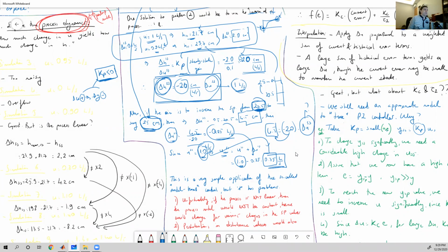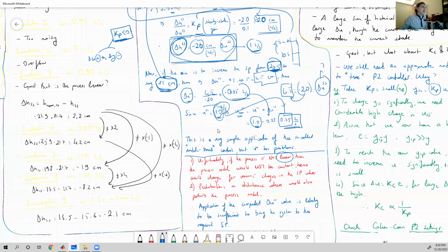Now, the most important problem here is this works only if the process is linear. Because if the process is nonlinear, such as the one that we have, the process parameters are likely to change from operating point to operating point. And I have already shown you that tau significantly changes from operating point to operating point. And maybe if you go through a sufficient number of different operating points, KP is also going to change. I haven't checked that out.